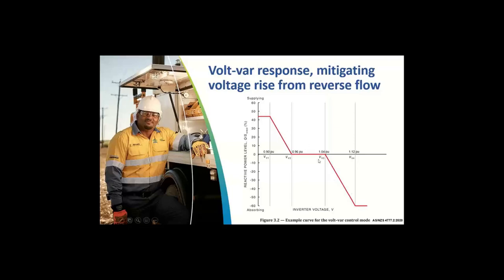This effectively allows the inverter to not only generate active power, but also act like an inductor at high voltages to create inductive load on the network and offset some of the voltage rise caused by active power injection, and has been very helpful for mitigating the voltage rise caused by distributed PV.